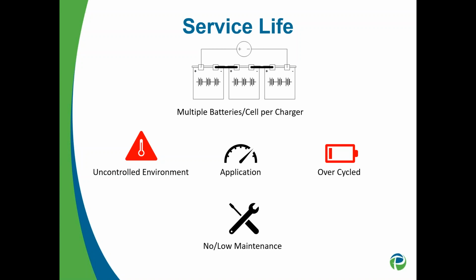In a data center, cooling is a tough thing, and it's one of the things that gets pushed aside because there's a lot of mechanical failures, so there's a lot of redundancy built in. Getting the right temperature in your battery room is kind of a second thought, so sometimes it's too high, sometimes it's too low. If the temperature is too high, you affect the health of your battery and its service life. If it's too low, you also lose - you may maintain a longer service life, but you'll lose capacity if it's too cold. So batteries are kind of a sensitive subject.